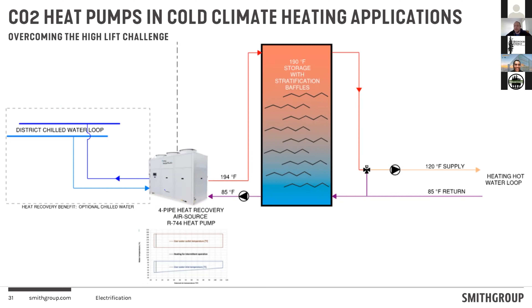The beauty of a CO2 heat pump is that because it's a transcritical CO2 heat pump, it's way up there in the transcritical zone. It's making very hot water at very low outside air temperatures if I'm in air source mode. It's a great technology that I can't wait to see deployed in cold climates, paired with thermal energy storage. Because what if I don't have to make hot water at the worst day condition when it's 0 degrees outside? What if I can wait 4 hours until it's 10 or 15 degrees outside? My COP goes up, my capacity goes up, and I've got the storage there waiting to accept it. So my big shout-out from the fireworks is: don't forget about thermal energy storage.